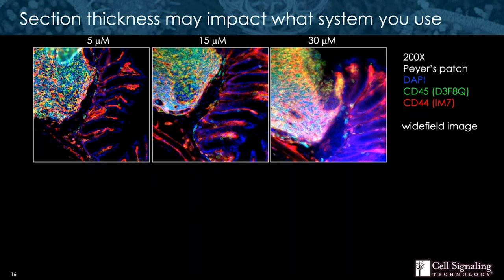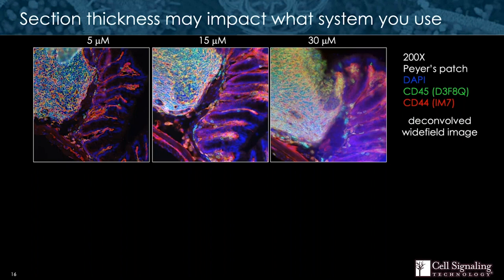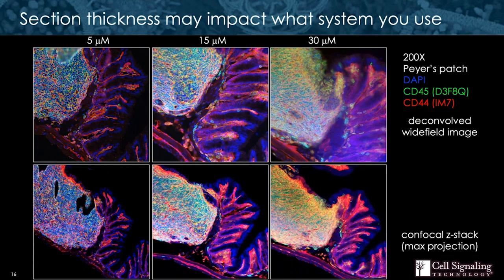The epifluorescent wide-field microscope collects light from the entire sample, and this can result in a blurry image when working with fixed sections or samples like organoids. You may be able to further resolve an image using deconvolution — a mathematical process that enhances resolution by identifying the out-of-focus light and reassigning it to its original location. Your microscope software may have a deconvolution option included, or you can bring your images to ImageJ and perform deconvolution there. This is definitely an instance where using a confocal gives an advantage over using a wide-field microscope. With very thick sections, even when I overlay all of the signal collected for each channel, the image is still relatively crisp compared to wide-field images.